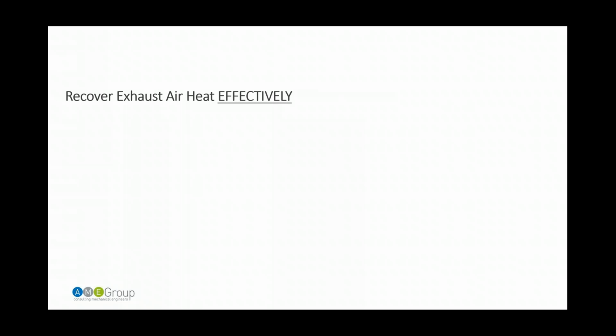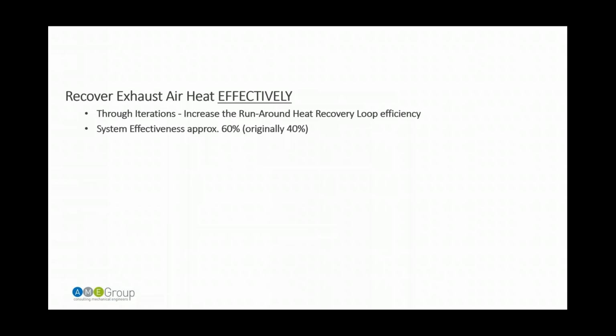So we've got a runaround loop that we've designed, and it was difficult to look at effective heat recovery that way. And so what we did was take our initial runaround loop that we were provided when we got selections for our heating or for our runaround coils, and we just went through some iterations of it. And we took our efficiency of that loop from about 40% up to 60%.